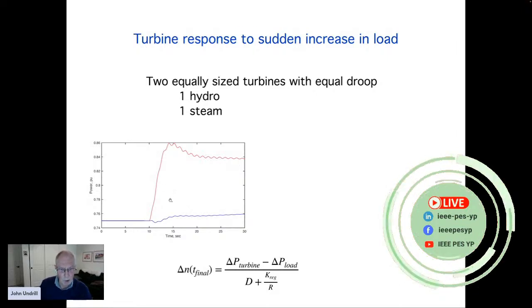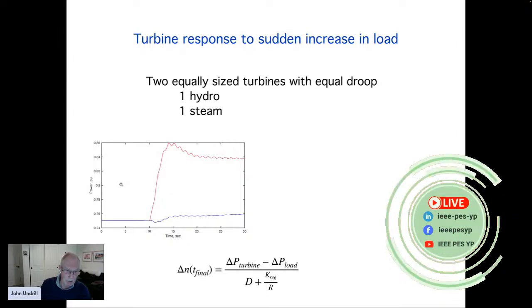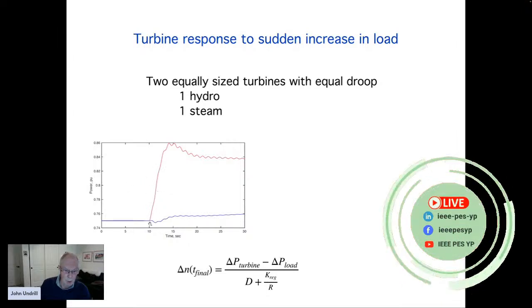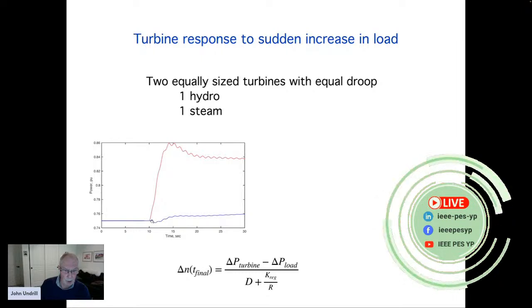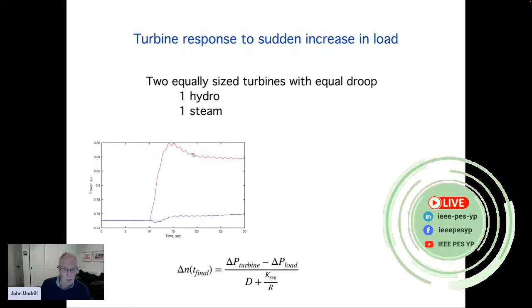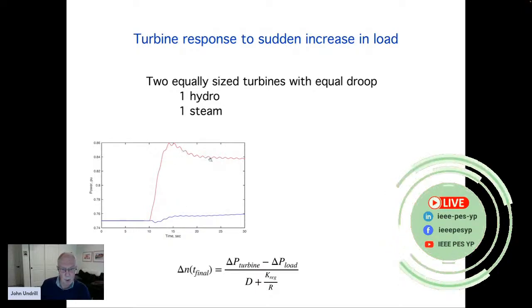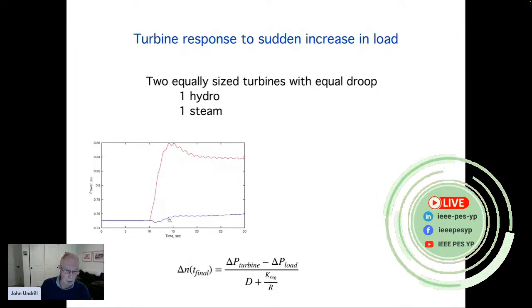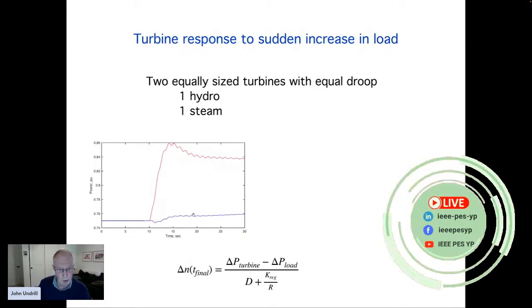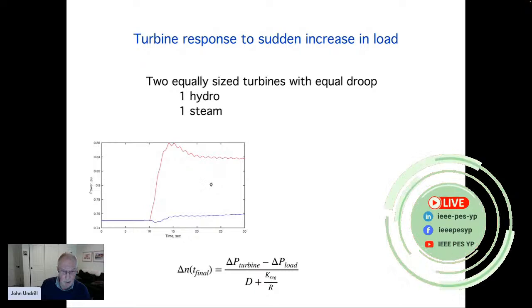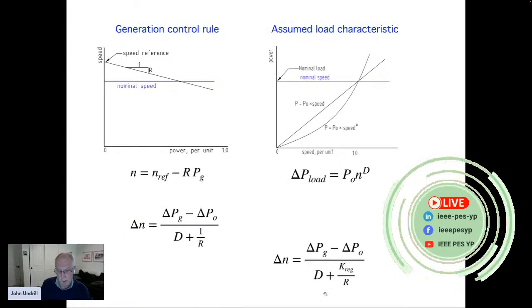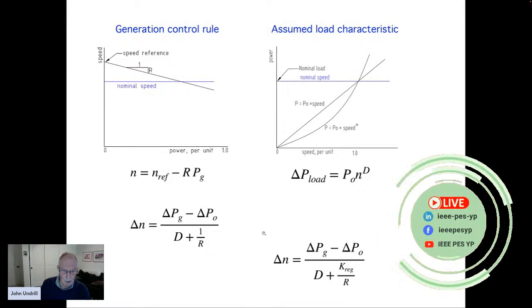Well, this is a simulation, but it's a pretty good simulation. Here's what happened. The load increased at the 10-second mark, and the generators did not go equally to their new load. One generator did most of the work, and the other generator was lazy. The red is characteristic of a steam turbine response to a sudden change. The blue is characteristic of a hydro turbine response to a sudden change. Our droop equation, this equation, or this equation, depending on who's regulating.